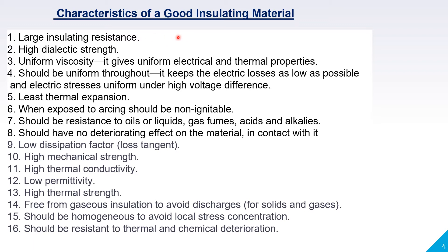What are the characteristics of a good insulating material? Large insulation resistance, high dielectric strength, uniform viscosity. It should be uniform throughout so that electrical losses are as low as possible and electrical stresses are minimized. It should have least thermal expansion, and when exposed to arcing it should be non-ignitable. Insulating materials should be resistant to oil, liquids, gas fumes, acids, and alkali. They should have low dissipation factor or loss tangent, high mechanical strength, high thermal conductivity, low permittivity, and high thermal strength.